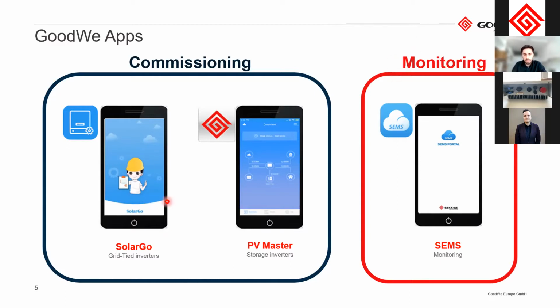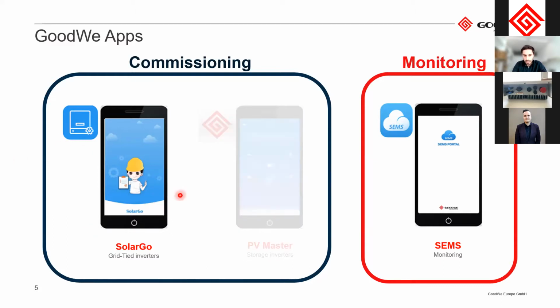Basically, there are 3 apps. You have 2 different apps for commissioning, and depending on whether you have a grid tie inverter or a storage inverter, you will use one or the other. The SEMS app is only used for monitoring; the other 2 are only for commissioning. For a grid tie inverter, you use the Solar Go app, and for a storage inverter, you use the PV Master app. Today, the SDT Generation 2 is a 3-phase grid tie inverter, so we will use the Solar Go app.